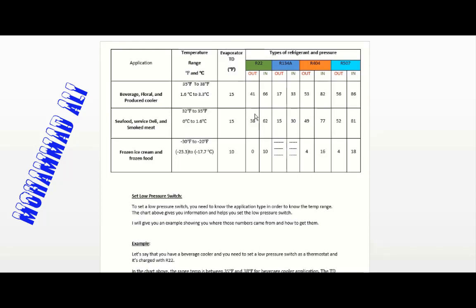I'll show you how to get those numbers for any type of refrigerant. You just need to know the type of application, the temperature range, and the TD — those stay the same. The pressures may change according to the type of refrigerant. In our example, we want to cool beverages at 35°F to 38°F with R22, and we'll find the cut-out pressure.